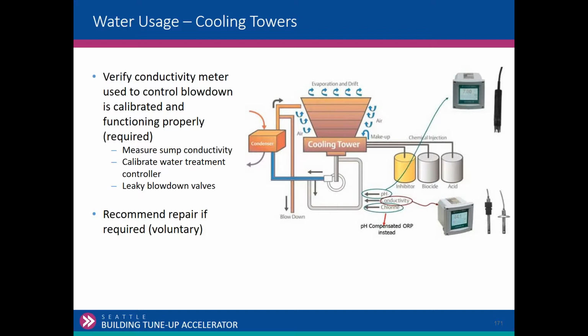So this is a system that can, and those are the required things: calibrate water treatment, leaky blowdown valves, replacement. And you can determine leaky blowdown valves if you've got water consumption, if your makeup water meter is running when the tower's off or not in demand, you're losing water out of your sump, like overnight, for example. And we can measure that.